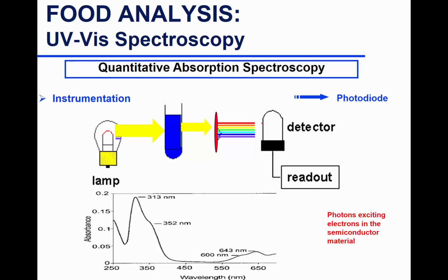Then it's not a monochromator. Scratch that. I am really tired today. It's a photodiode array. So this is an array of diodes. The light will hit an array of diodes, and then each wavelength is going to be transmitted as an electric signal separately into the detector, and you get a readout.